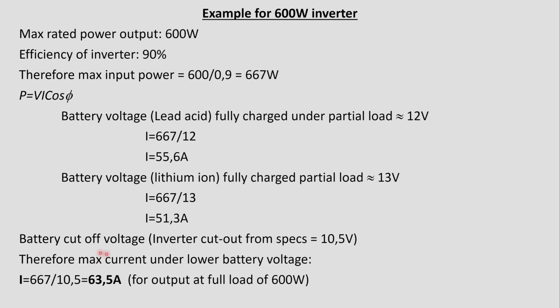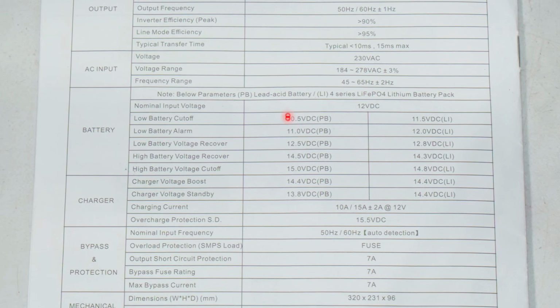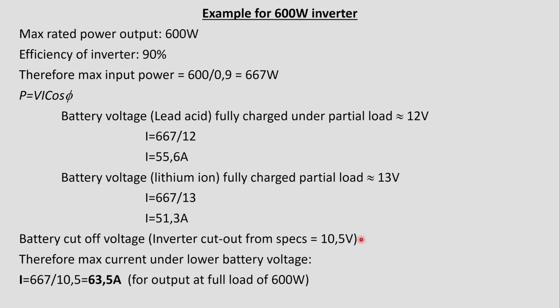So let's look at the battery cutoff voltage. Now, according to the specification, the cutoff voltage is 10.5 volts for lead and 11.5 volts for lithium. Now, I'm going to use the lead because that is a lower voltage, which means that has a higher current. So let's look here. The maximum current with a lower voltage of 10.5 volts is now a higher current because the power output has to remain the same. It's just that the battery has to work harder to give that current. I'm still using 667 watts, but now I'm dividing that by 10.5 volts, and that gives me a current of 63.5 amps. So that is the rated full load input current to the unit when it is providing 600 watts.